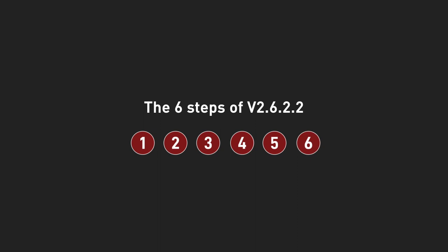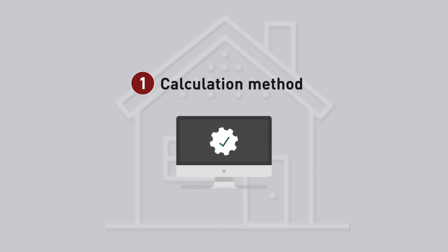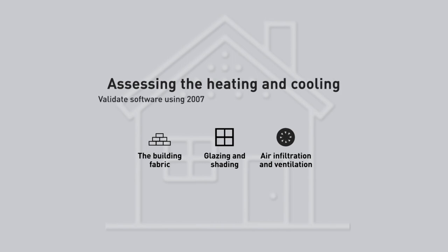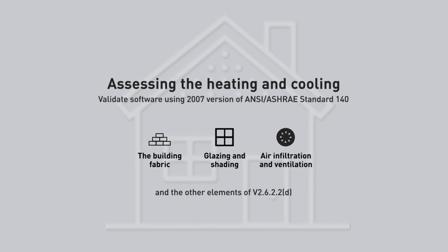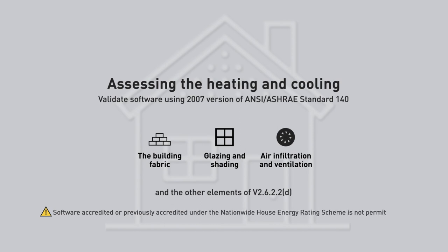Let's step through an example of using this method. It's made up of six steps. Step one is selecting a calculation method. The software program used must be validated and be capable of assessing the heating and cooling load by modelling the building fabric, glazing and shading, air infiltration and ventilation, and the other elements included in V2.6.2.2 Part D. House energy rating software accredited or previously accredited under the Nationwide House Energy Rating Scheme or NatHERS are not permitted for this method.